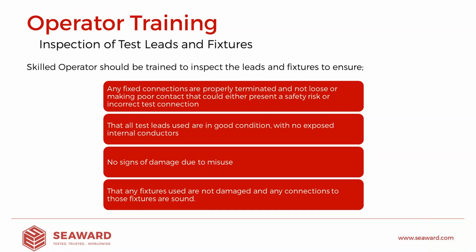So if the probe's been dropped on the floor, is it starting to crack or show signs of stress? Or any fixtures that you use. So if you do make any test jigs that have physical connections to the testing equipment, again, any signs of damage or misuse, any exposed conductors that could pose a safety hazard, the operator should be trained to spot those and ultimately then make that decision to take them out of service or make contact with a relevant person, maybe a maintenance or production engineer, who could come and correct the issue before further testing takes place.